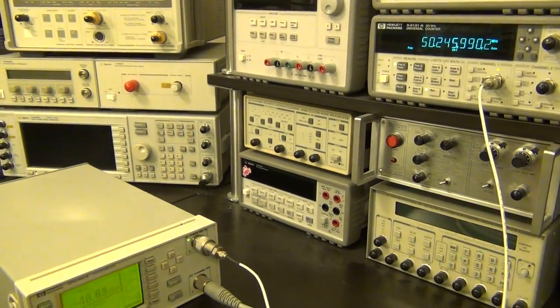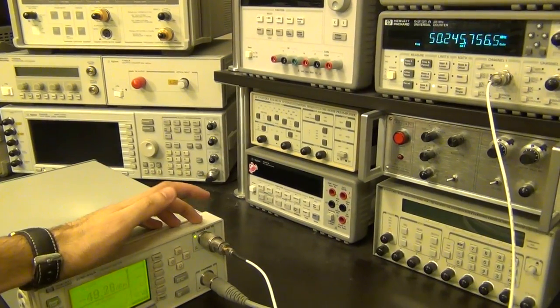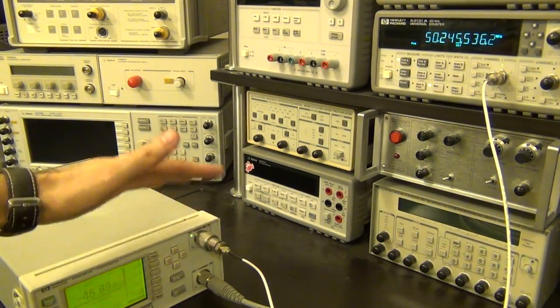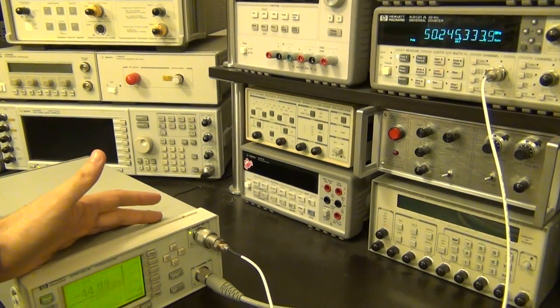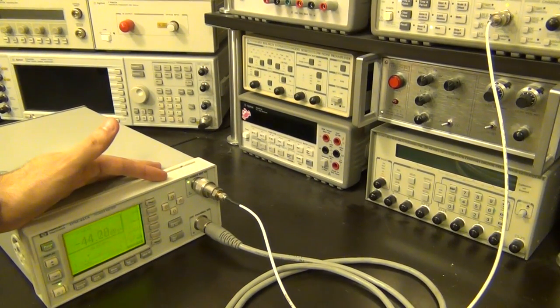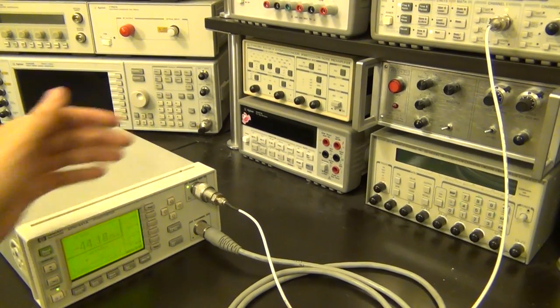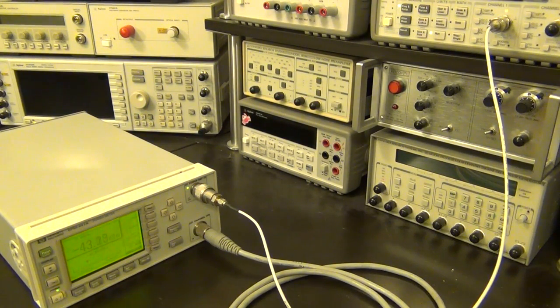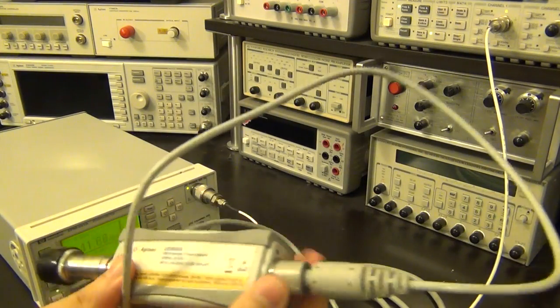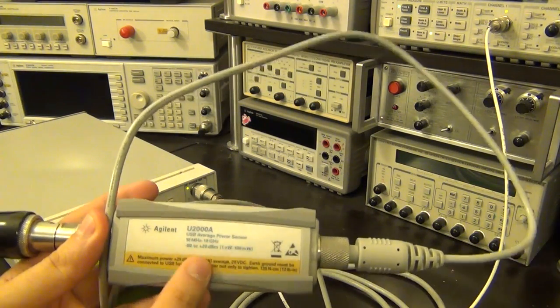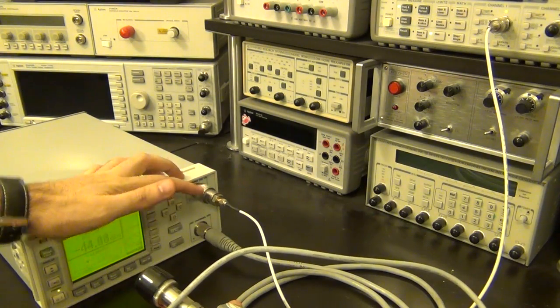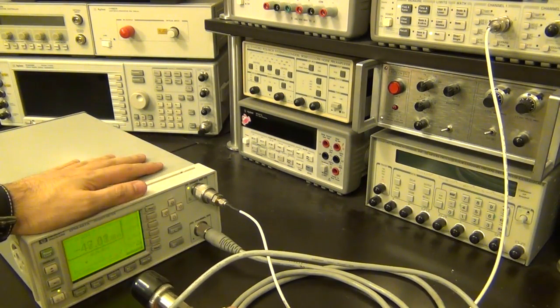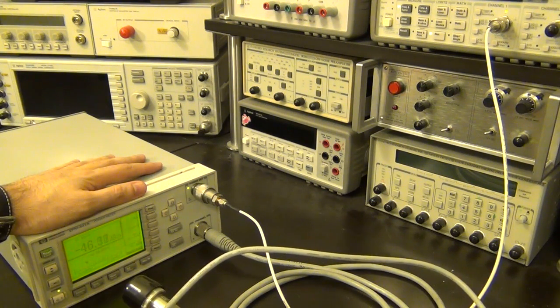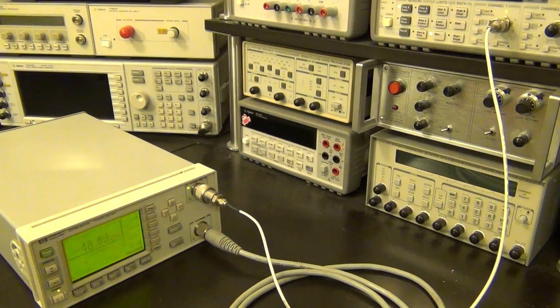What is more important is that the power coming out is indeed 0 dBm or 1 milliwatt. In order to check that, I have to check it with a totally independent power sensor, which is calibrated by another calibrated 50 megahertz reference. So like I said, my USB power sensor is very nicely calibrated. So I'm going to use this guy connected by USB to the computer, and you can see this is the USB cable connected to it. I'm going to use a U2001A, which is nicely calibrated, to make sure that this is 1 milliwatt. And if it is, then we can declare this repair a success, and I think that would be pretty awesome. So let me go ahead and switch the setup and take a look at that.